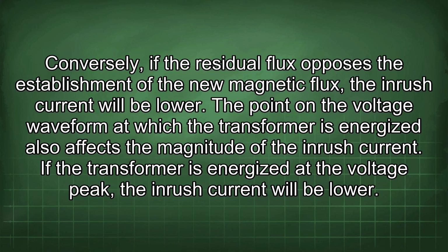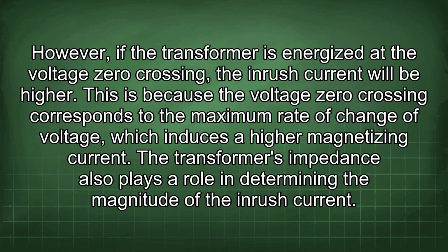The point on the voltage waveform at which the transformer is energized also affects the magnitude of the inrush current. If the transformer is energized at the voltage peak, the inrush current will be lower. However, if the transformer is energized at the voltage zero crossing, the inrush current will be higher. This is because the voltage zero crossing corresponds to the maximum rate of change of voltage, which induces a higher magnetizing current.